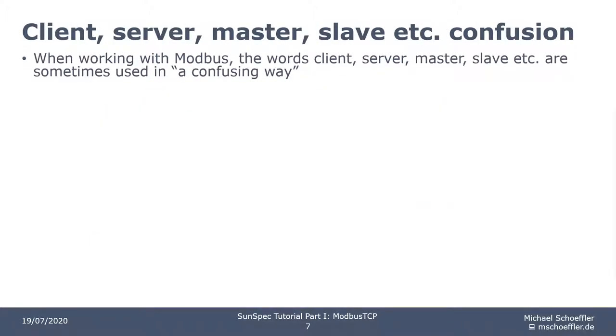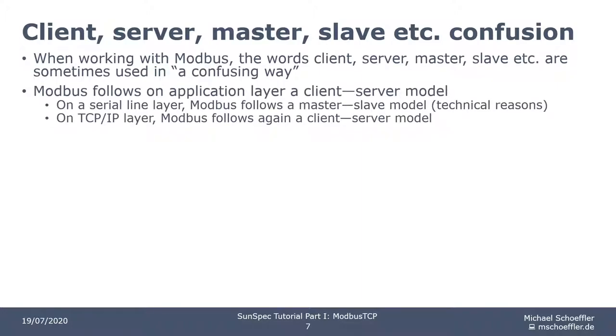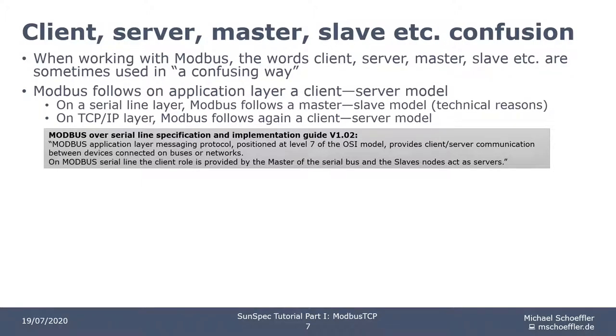If you start working with Modbus, you might get confused when you come across the terms client, server, master, and slave. Unfortunately, they are not always used in a consistent way within the Modbus community. At the application layer, Modbus follows a client-server model. If the underlying communication protocol belongs to the serial line part, a master-slave model is used, which has technical reasons. If the underlying communication protocol is TCP/IP, Modbus uses again a client-server model. Modbus makes this clear in the serial line specification: the Modbus application layer messaging protocol, positioned at level 7 of the OSI model, provides client-server communication. On Modbus serial line, the client role is provided by the master of the serial line bus, and the slave nodes act as servers.